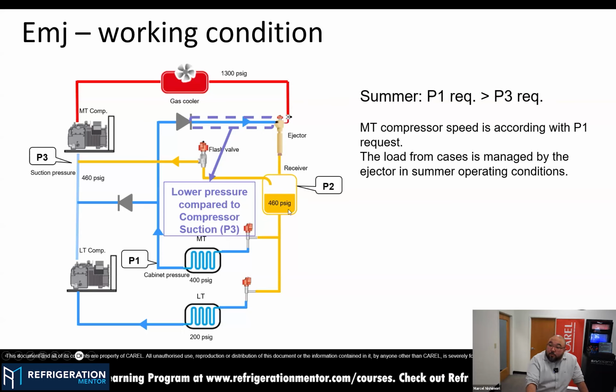And then from the liquid receiver, like 460 PSI, going straight to the compressor. We will see that we have a dedicated flash gas bypass logic to make sure that when we are engaged, so ejector mode, the flow here will have a very, very low pressure drop at the flash gas bypass valve. So all the refrigerant will go here. And at this point, this suction pressure will be higher, and we need a check valve here to avoid flow back from the MT line to the MT suction cases. So this is the reason why we have this check valve here, okay?